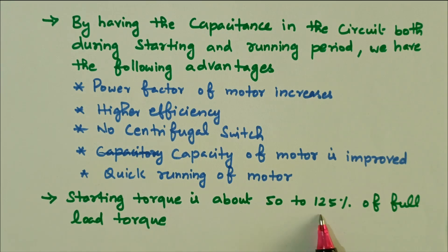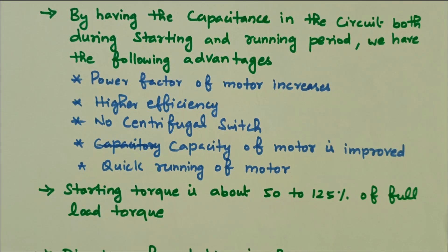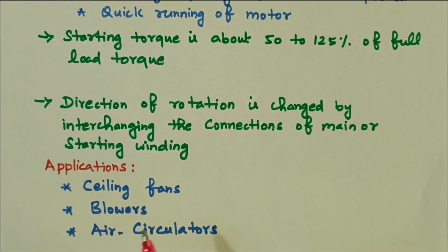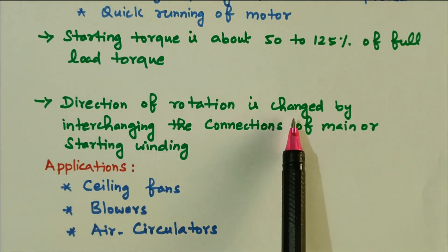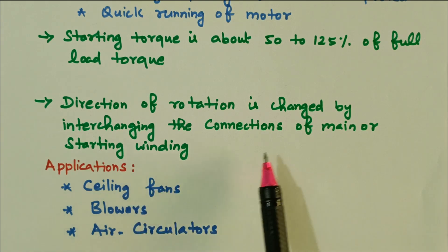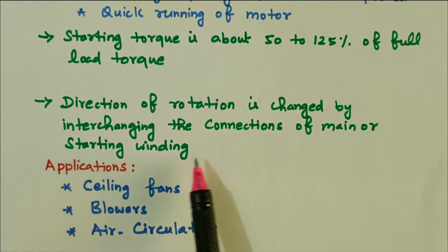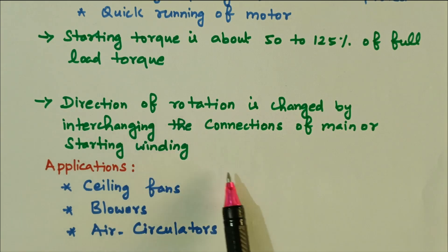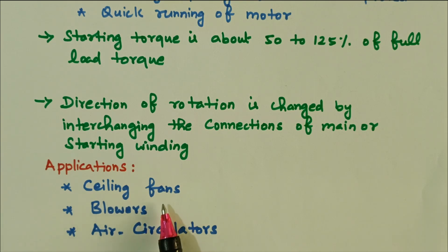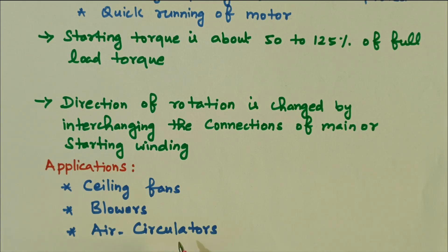The starting torque is approximately 125 percent. The direction of rotation is changed by interchanging the connection of the main or starting winding — if you reverse either winding, the direction of rotation is also reversed. Applications include ceiling fans — in the ceiling fan, a capacitor is present and remains connected during running — as well as blowers and air circulators.